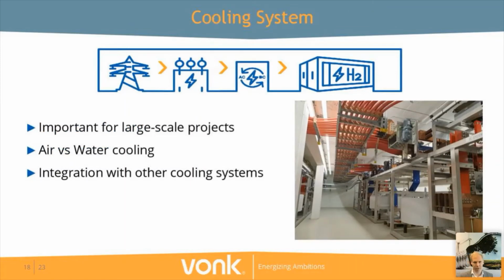From the transformer, we go to the cooling system. Even though our systems, as we build them, are very efficient, as you could see in an earlier screen, we can reach up to 98% of efficiency. You have to look at it from a size perspective. For instance, if you're having an electrolyzer plant which is 100 megawatts, even at 98% efficiency, you still have 2 megawatts of heat dissipation. This obviously means cooling is an important aspect to take into account.